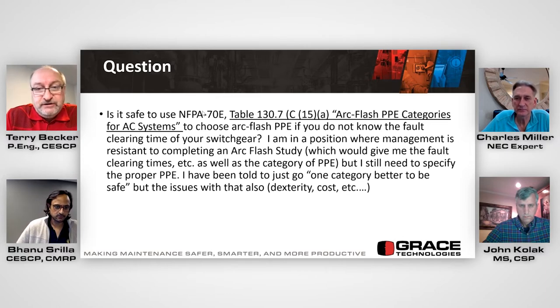And if you're working downstream of an electrical protective device, based on what the table provides, you make an assumption that it's going to open in that clearing time, right? Because the table is independent of confirming condition of maintenance. That's another topic, a risk-based discussion, and using the tables too. And then you use the tables.